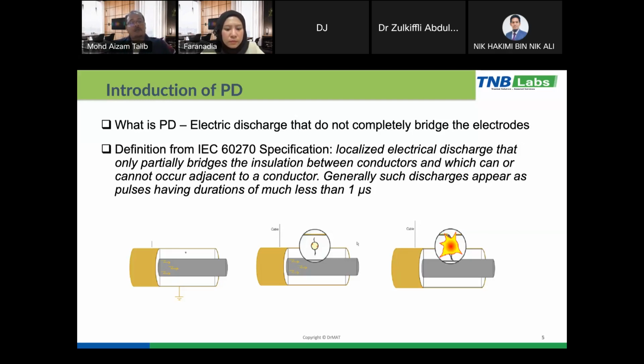So what is the definition of PD in IEC 60270? The IEC defines the PD as a localized electrical discharge that only partially bridges the insulation between conductors. When we design the equipment, we have a distance between the high voltage and the low voltage, and between the high voltage and low voltage to the ground. So partial discharge only partially bridges the insulation between the conductors, which can or cannot occur adjacent to the conductor. Generally, the discharge appears as a pulse, and it has a duration of less than a microsecond. It is very small and very fast.